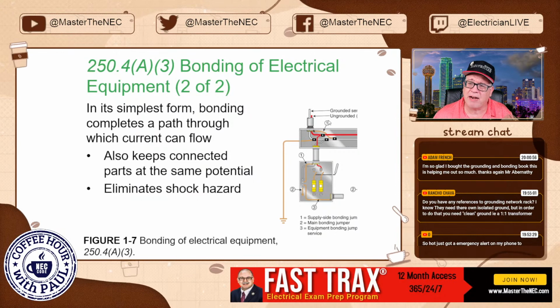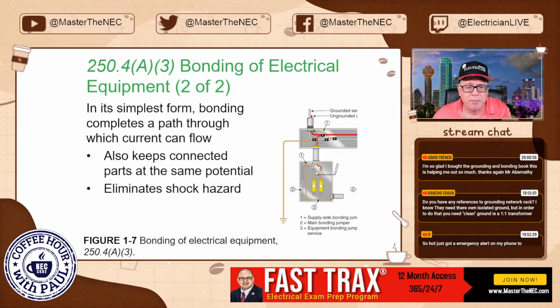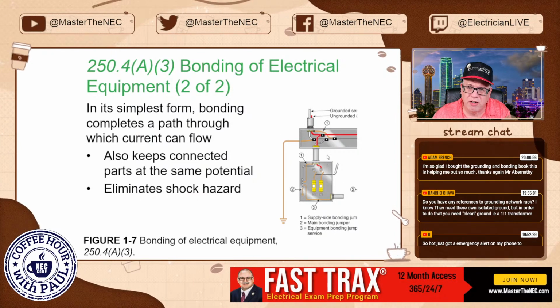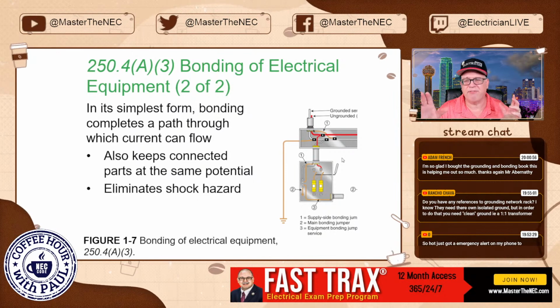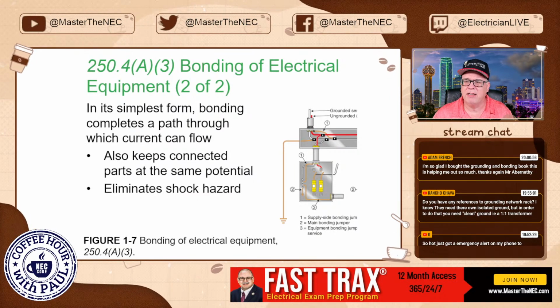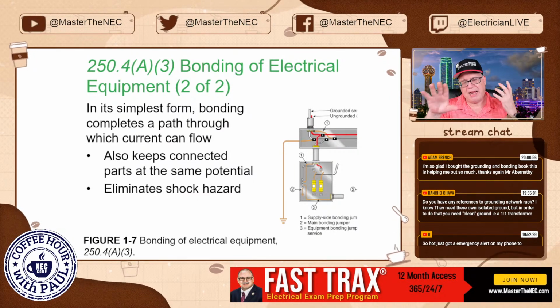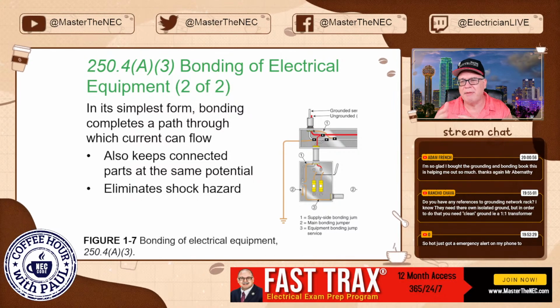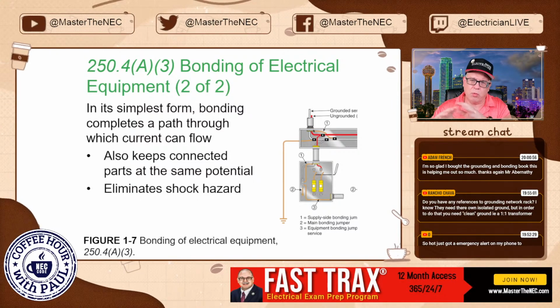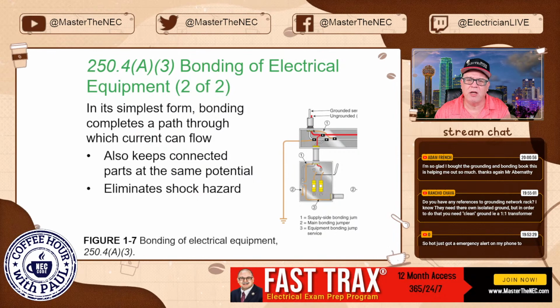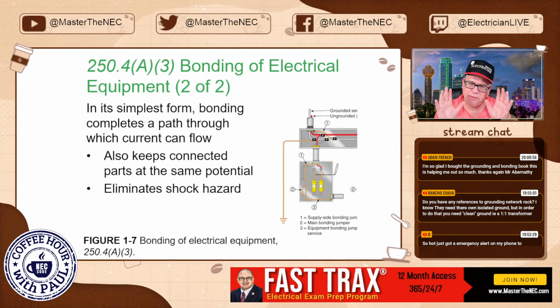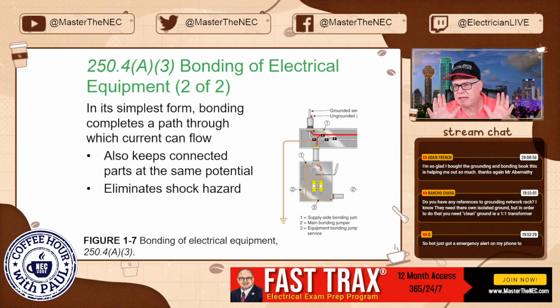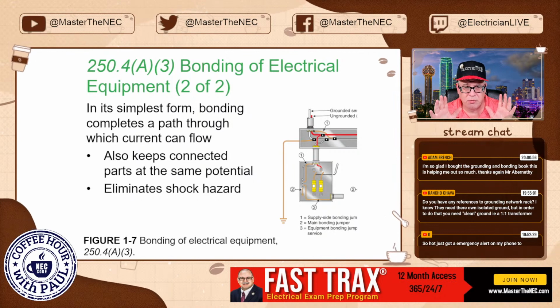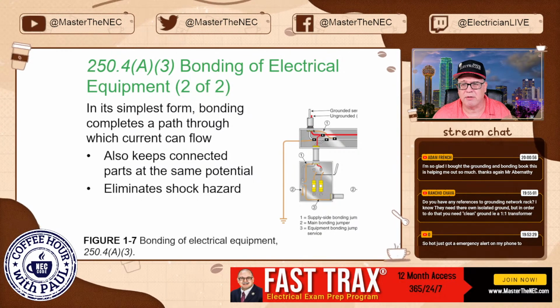Take this example right here. Everything's bonded properly. If you touch here and you touch here, you're not going to feel a shock, if everything's done right. If you have a poor connection, something could happen. To eliminate the shock hazard in an isolated system like this, you make sure everything is bonded back, so that in case something gets on the metal enclosure that's not supposed to, we're going to clear that breaker.